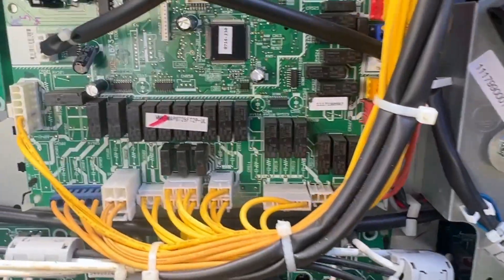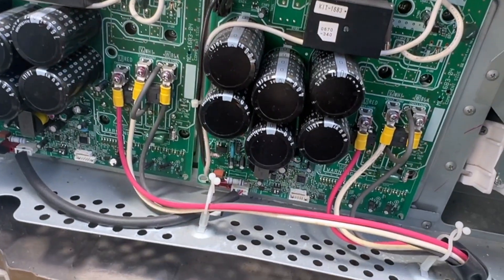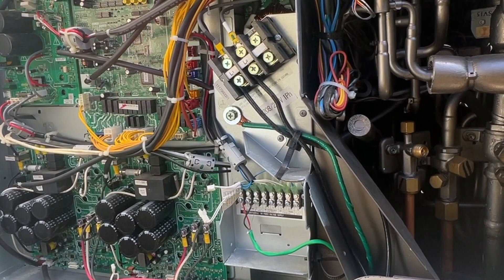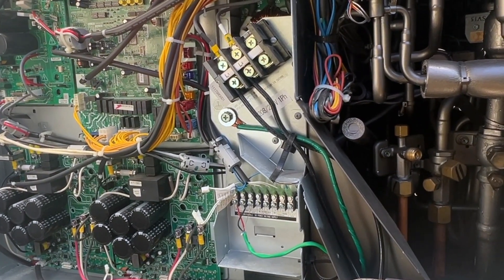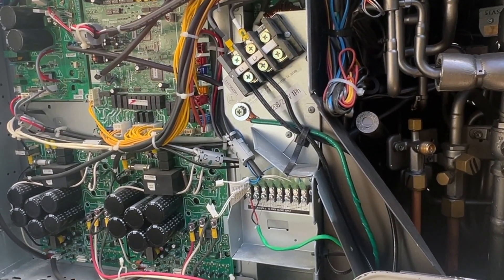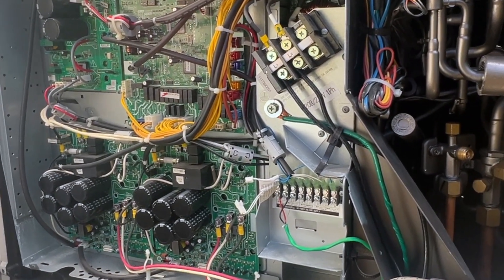What is up YouTube? Got myself a Toshiba VRF system. We're gonna have to readdress everything here on the dials. We had a unit that had to be replaced because they're doing remodeling — this was their office building. They replaced the indoor cassette unit to a ducted unit, and we need to readdress the system and find all the thermostats and units all over again.